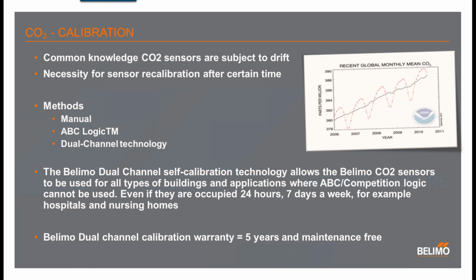Belimo air quality sensors. It is common knowledge that CO2 sensors are subject to drift and a necessity for sensor recalibration after a certain amount of time. The methods can include manual calibration, ABC logic, and also dual channel technology.